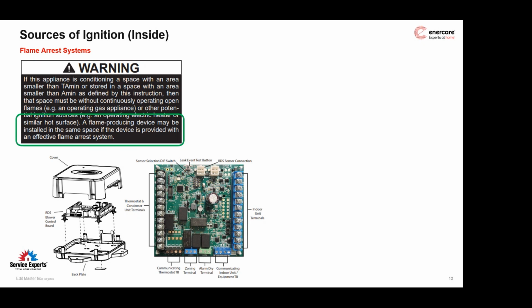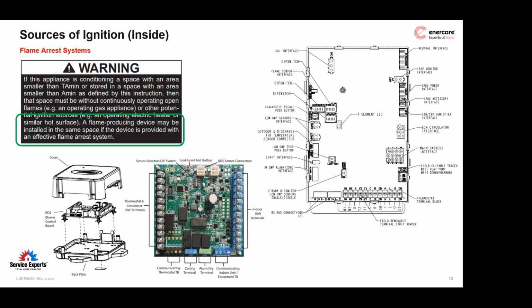And then Lennox has a couple of versions. They have a 24-volt version and a communicating version. And then for those furnaces that are either already installed or being installed with your system, I'm going to use Lennox as our primary example, as I said earlier. This is their SLP control board, at least an image of it. It has a couple of sensor locations right here and the push button right here for the test.